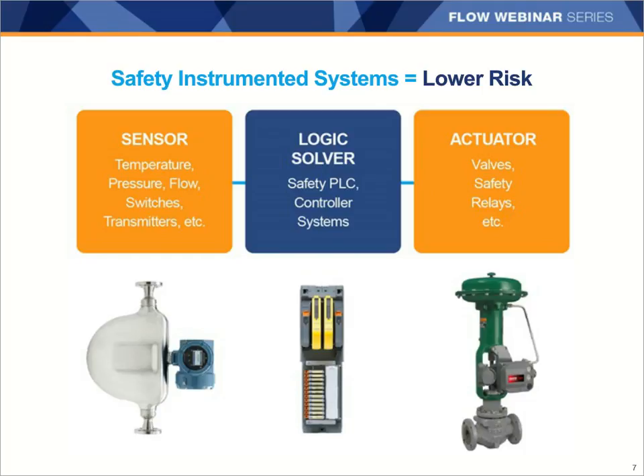So just as a basic overview, there are 3 elements in a safety instrumented system: a sensor, a logic solver, and a final control element. As you know, the sensor is the part that collects information necessary to determine if an emergency situation exists. The purpose of these sensors is to measure process parameters like temperature, pressure, flow, and other parameters to determine if the equipment or the process is operating in a safe state. The logic solver is what decides what to do with the information from the sensor, and it sends a signal to the final control element or actuator to take an action to establish a safe state of operation.